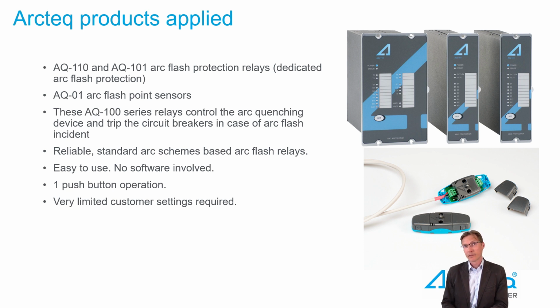Having a dedicated relay provides reliability. The system is based on the standard arc schemes, very easy to use relays, no setting software involved. Only one single push button operation. And for the sake of simplicity, very limited customer settings required. This is especially important since most of the nuisance trippings in the system, if any, are caused by wrong settings. Here with the AQ100 devices, which are controlling the arc quenching device, we have eliminated almost all the customer settings.